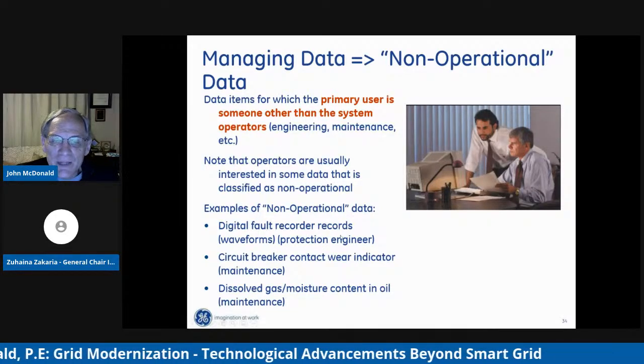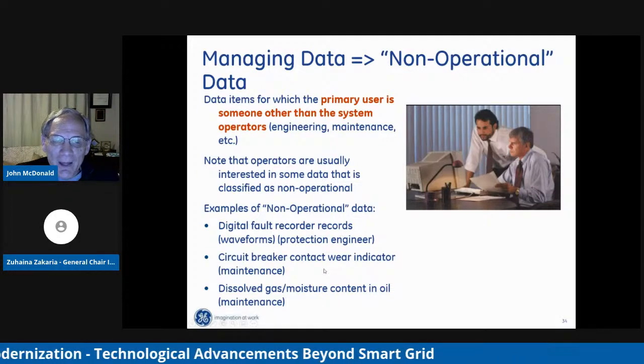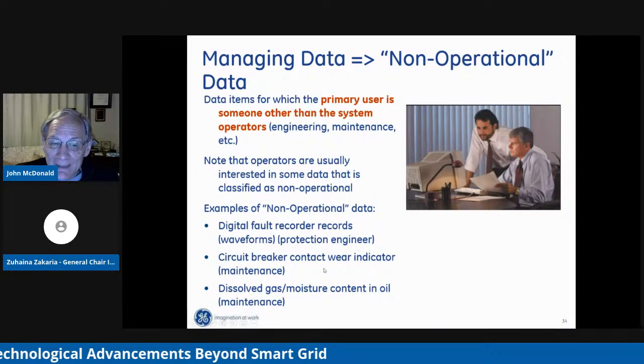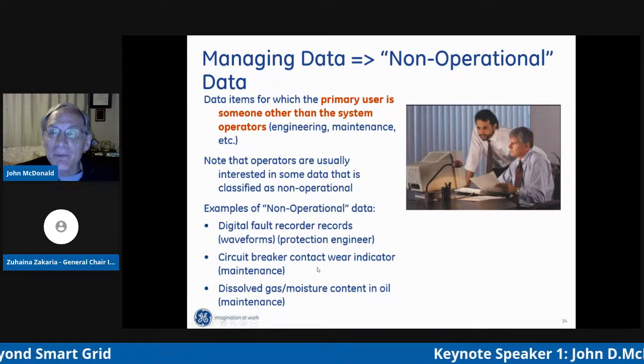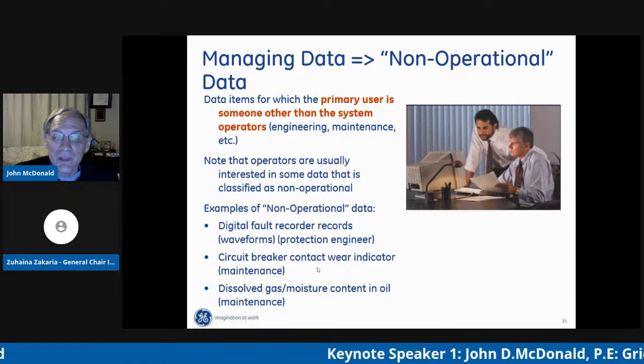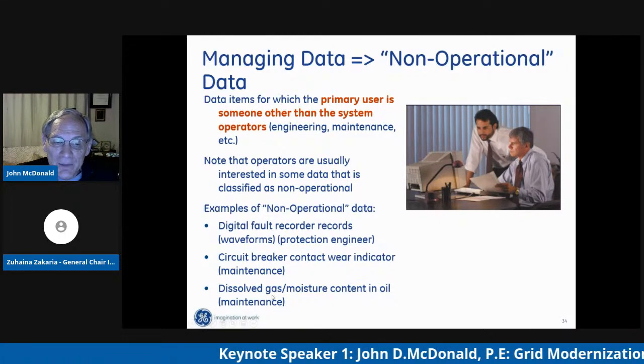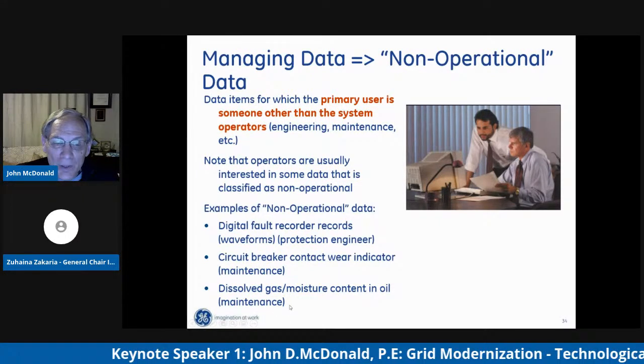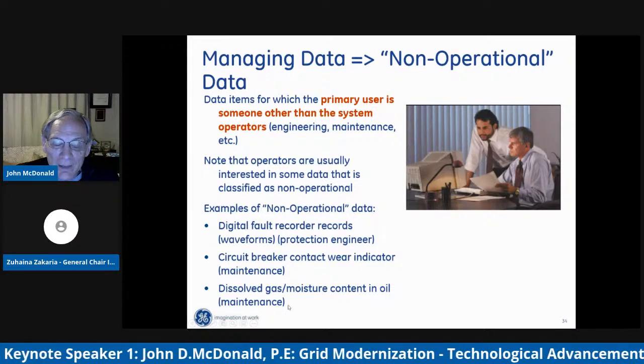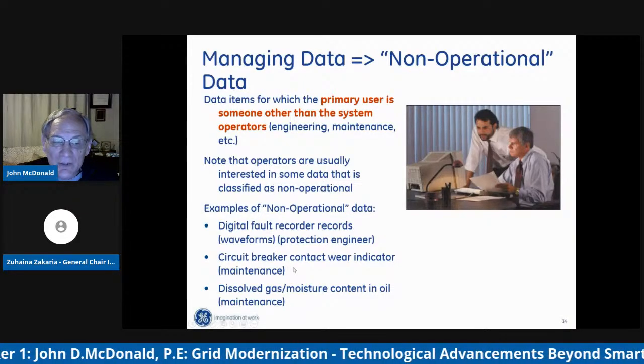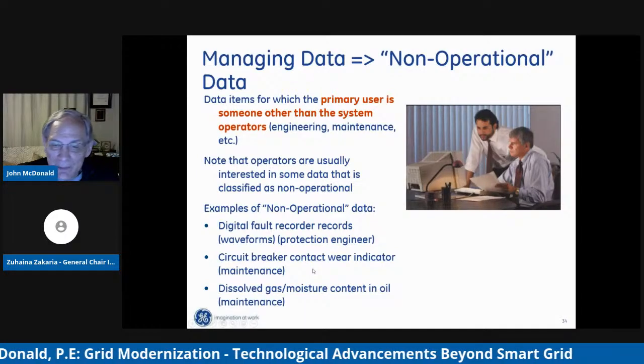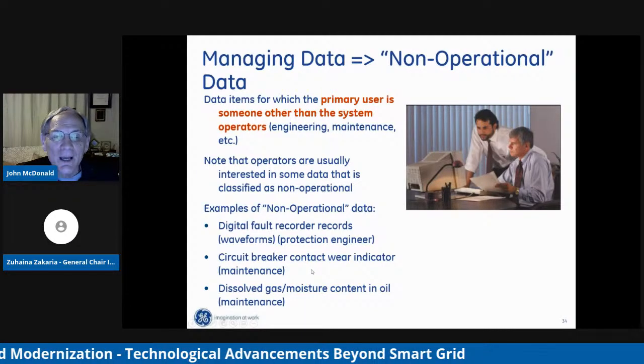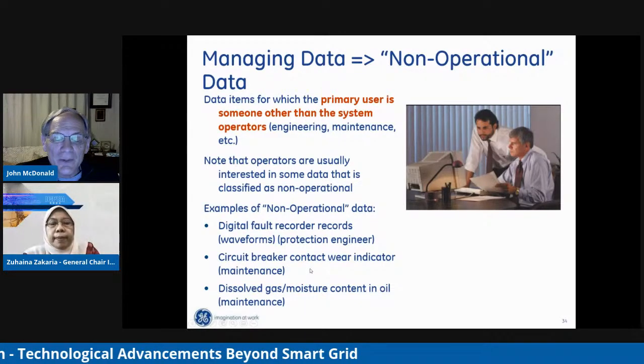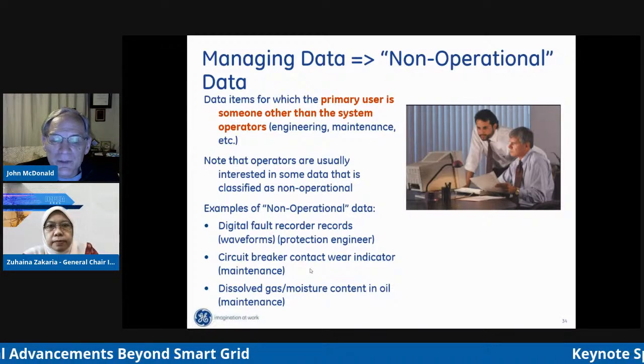Example would be a digitized waveform from a relay, the I2T information for a circuit breaker in a relay, the operations counter in the relay for that circuit breaker, dissolved gas and moisture content in oil in a monitoring and diagnostic device, and circuit breaker contact wear indicators like I2T. This is very important information.